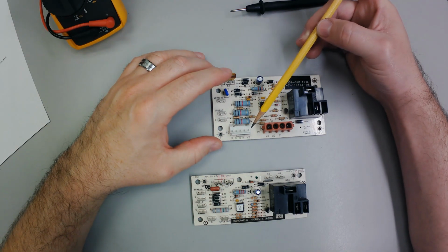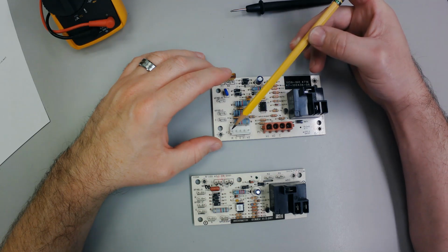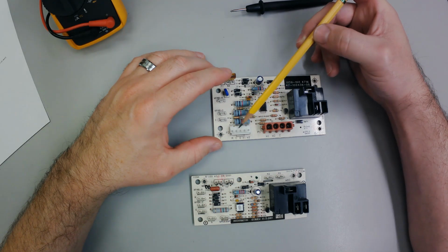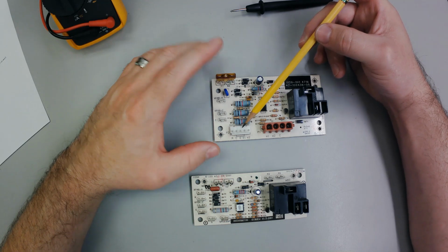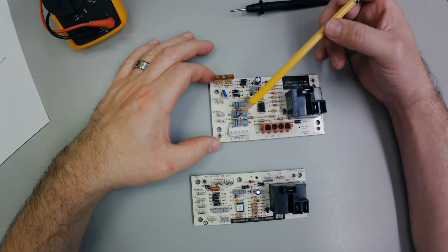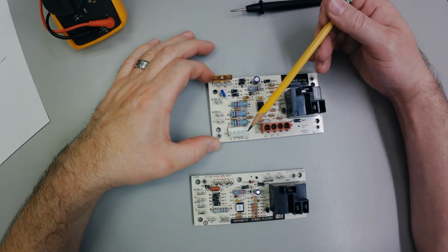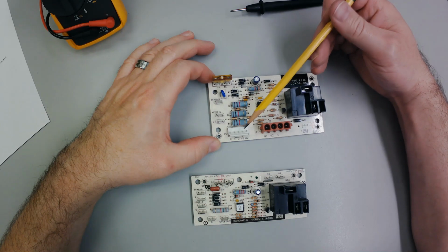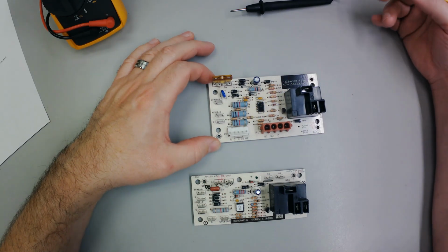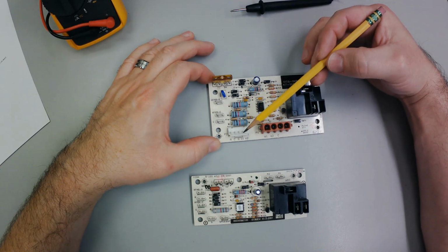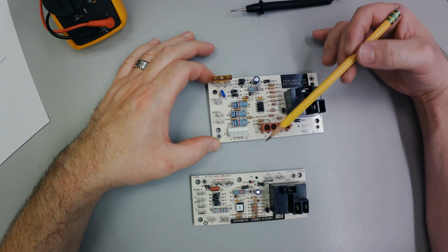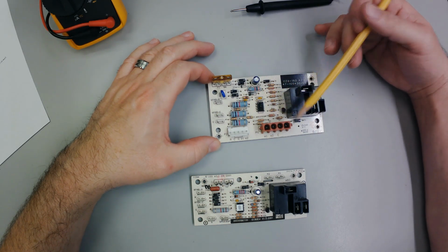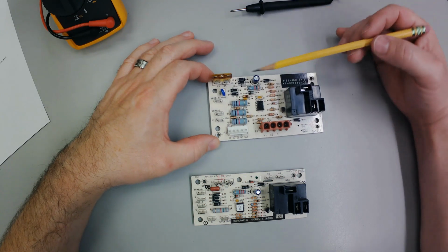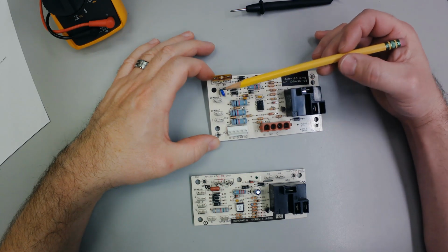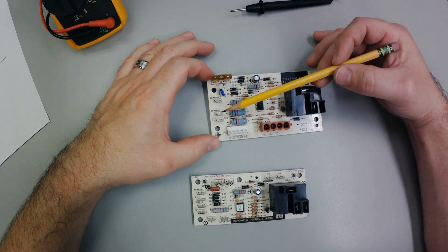These are coming in. So these terminals here, or this plug here, is going to deal mainly with your thermostat connections. All right. And most of them are coming back in. Okay, if you follow my logic and my flow of power, this G is coming back in along with the W's to tell the board to work, to tell the sequencer to work. All right. So transformer R comes in. Transformer common, for me, that's going back out.